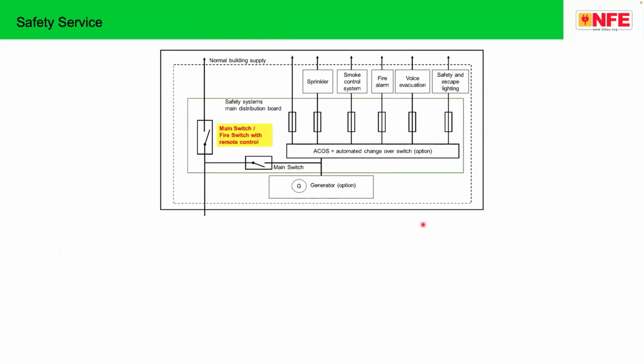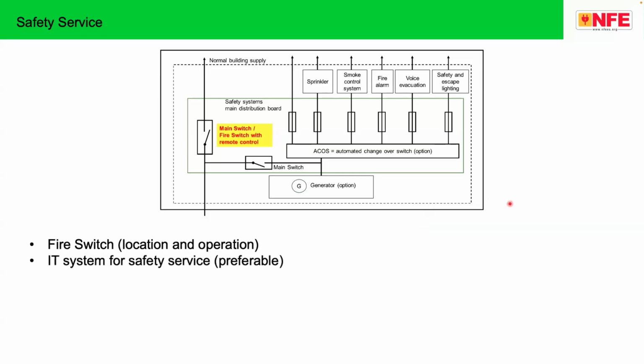Safety service. It is a requirement in the Indian safety regulation that in an accessible position, there should be a switch which can be operated during an emergency. And with one switch, the entire supply to the building can be disconnected, except the safety service. Now, in this particular subject, the interesting points which we need to take care of: first, the location and the operation of the fire switch, who can operate it, where it is kept.